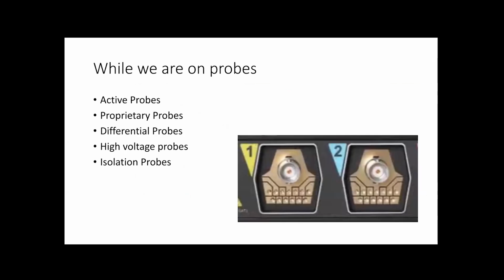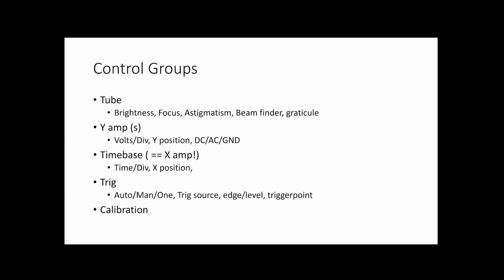And while we're talking about probes, there's umpteen other types of probes. You get active probes, you get proprietary probes, made by Tektronix and Rigol and all these people. You get differential probes for measuring the difference between two signals rather than an absolute signal. You get ones for doing high voltages, you get isolating probes, there's umpteen of them. That there's a Rigol oscilloscope, and as you can see, you can just plug a BNC into it as normal. But if you've got the special Rigol probe, then when you plug the BNC in, all these other connections get made, and your scope probe has got amplifiers and logic and all sorts of stuff on it, and you can do other things that you can't do with a more conventional oscilloscope probe. Most of those other scope probes, by the way, are big, big money.